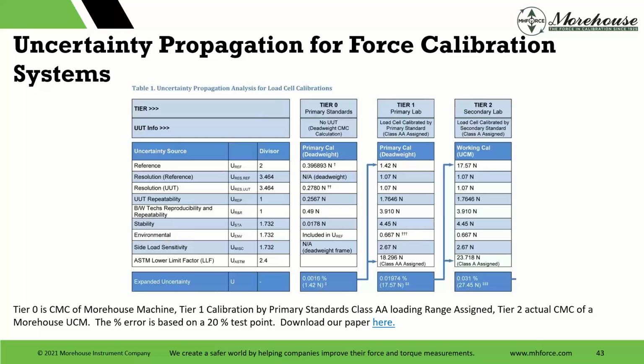99% of the time, here's the uncertainty statement that's gonna baffle everybody, but 99% of the time, I think it's great to be conservative, to give yourself a little bit of fudge factor. And then people say, what about the other 1%? Well, the other 1% is evaluating what matters and what doesn't matter. And sometimes, for example, one of the weights in one of our dead weight machines has more bias than the other ones. And if I claim 20 parts per million on this dead weight machine, I'm in. When I use that weight, I give myself no wiggle room. But when I use any other weight in the machine, I have a ton of wiggle room.